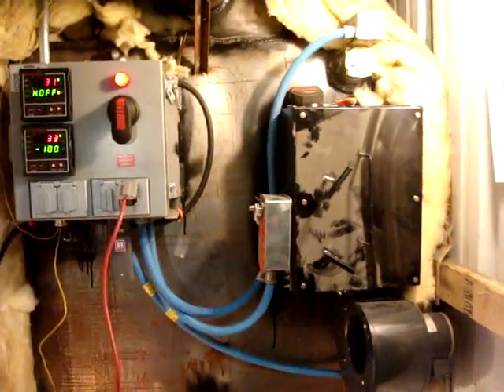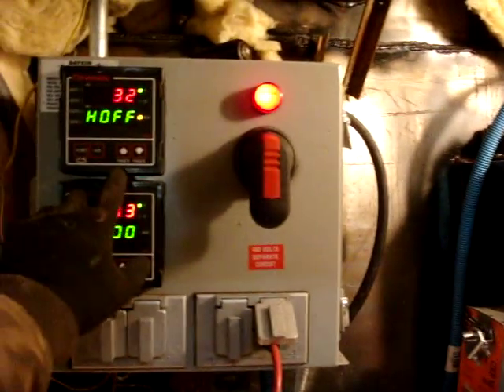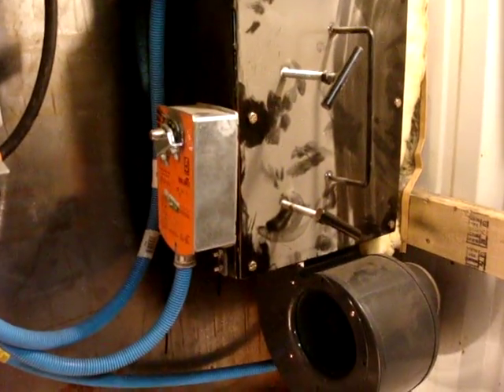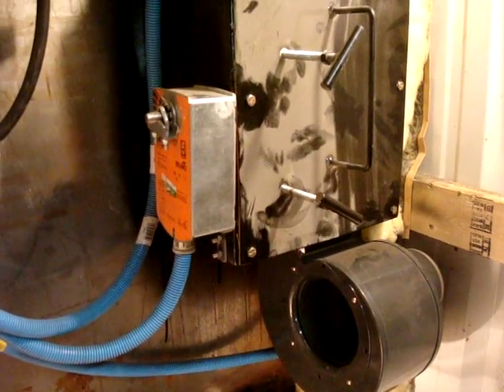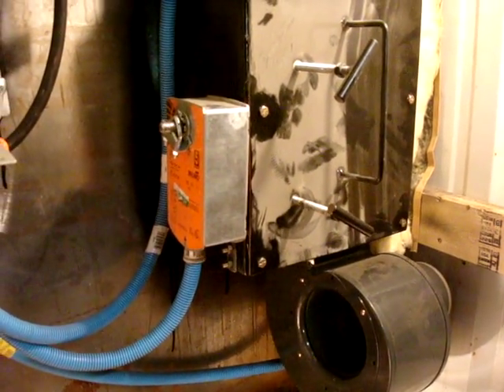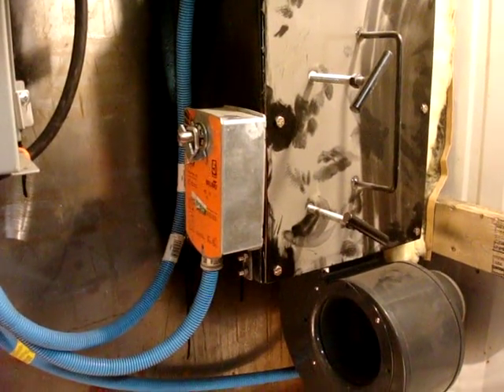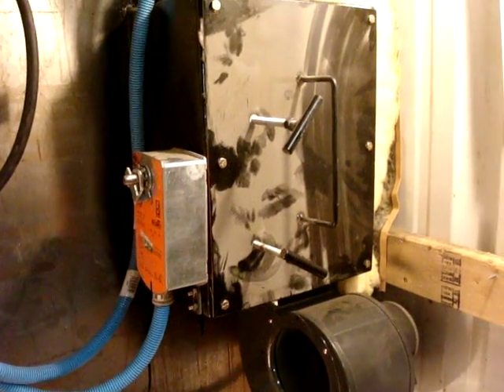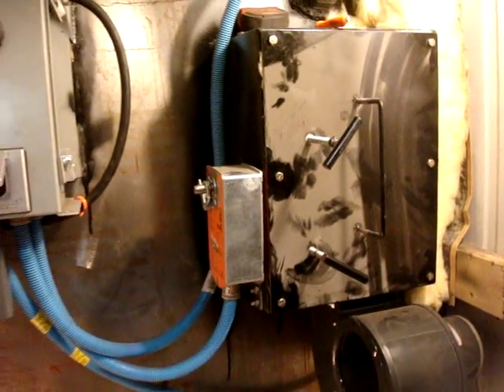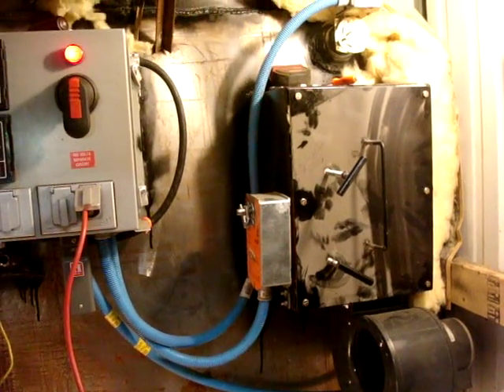I had the controller toggled off, but this will always be on — I'll turn it back on. The damper opens and the blower comes on. The damper is now fully open, the blower is running, pressurizing the airbox and pushing air into the air tubes, into the gas chamber, and into the firebox.